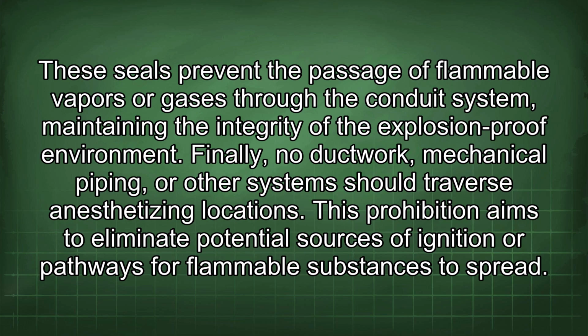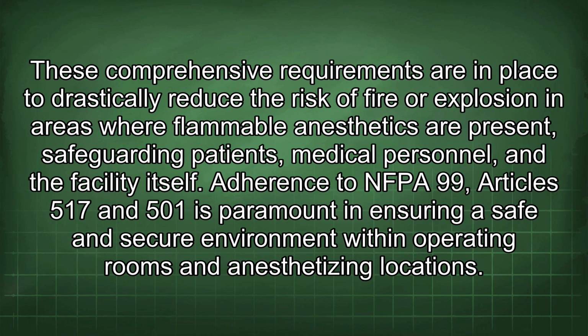Finally, no ductwork, mechanical piping, or other systems should traverse anesthetizing locations. This prohibition aims to eliminate potential sources of ignition or pathways for flammable substances to spread. These comprehensive requirements are in place to drastically reduce the risk of fire or explosion in areas where flammable anesthetics are present, safeguarding patients, medical personnel, and the facility itself. Adherence to NFPA 99, Articles 517 and 501 is paramount in ensuring a safe and secure environment within operating rooms and anesthetizing locations.